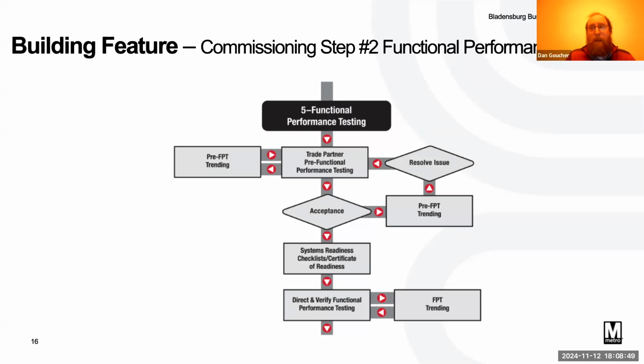Sometimes issues pop up, and we have to correct those through the issue resolution process. Once we're satisfied internally, we call the commissioning agent and WMATA, and then we have what we consider the formal functional performance test, which is witnessed by everybody. Again, sometimes issues still pop up, so we go through issue resolution, and eventually we get to an acceptable functional performance test. Everybody signs off on it, and that one piece of equipment is good to go.